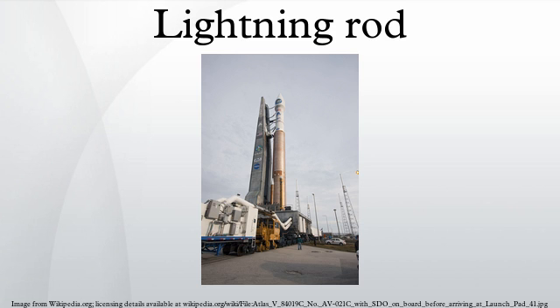Work performed by Charles B. Moore et al. in 2000 has helped this issue, finding that moderately rounded or blunt-tipped lightning rods act as marginally better strike receptors. As a result, round-tipped rods are installed the majority of the time on new systems in the United States. To quote, "Calculations of the relative strengths of the electric fields above similarly exposed sharp and blunt rods show that while the fields are much stronger at the tip of a sharp rod prior to any emissions, they decrease more rapidly with distance.